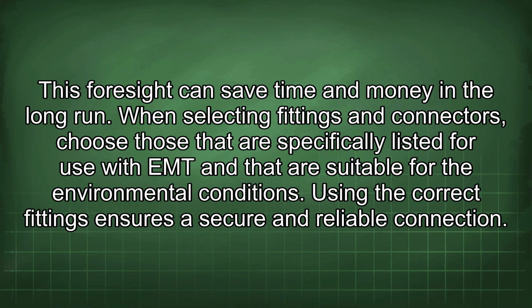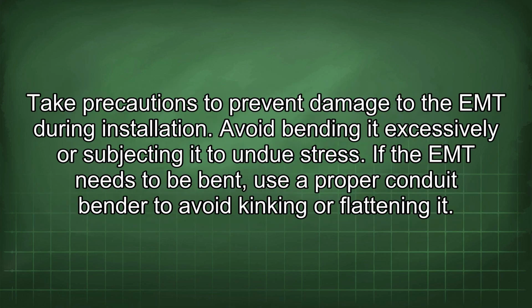When selecting fittings and connectors, choose those that are specifically listed for use with EMT and that are suitable for the environmental conditions. Using the correct fittings ensures a secure and reliable connection. Take precautions to prevent damage to the EMT during installation. Avoid bending it excessively or subjecting it to undue stress. If the EMT needs to be bent, use a proper conduit bender to avoid kinking or flattening it.